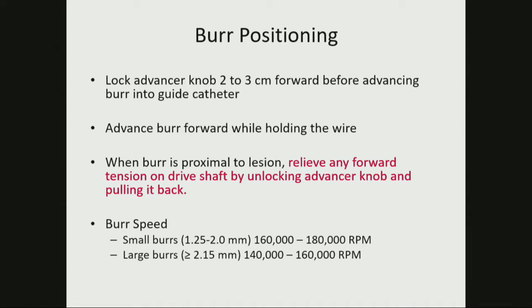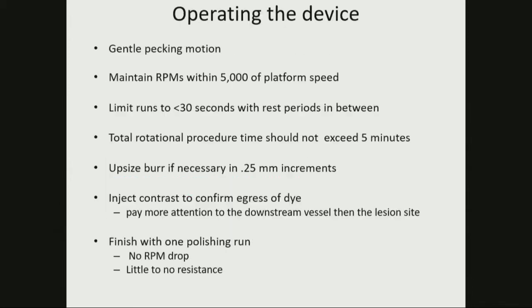When the burr is proximal to the lesion, relieve any forward tension on the drive shaft by unlocking the advancer knob and pulling it back. It's very important. Otherwise, if there's tension in the shaft, when you start rotablation it will jump into the lesion and can stall there. Burr speed: if it is 1.25 to 2, then 160 to 180,000. If it is a large burr, it is a little less than this.